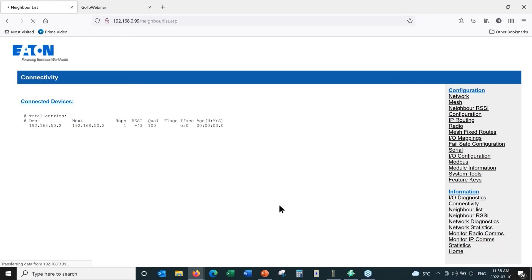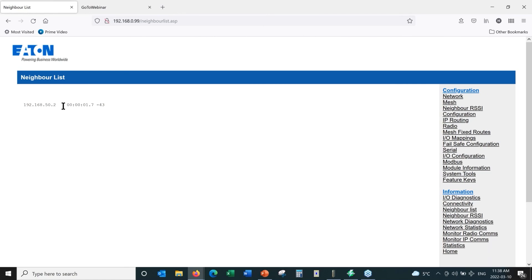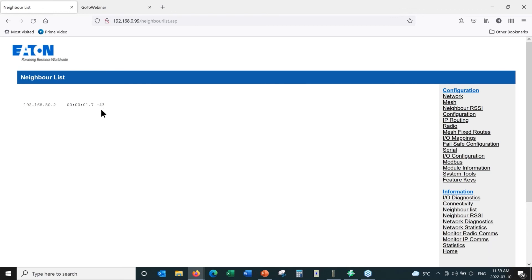The neighbor list shows a single remote radio with a radio IP address of 50.2. It has been online — the last transmission received was 1.7 seconds prior to clicking on this page. This tells you the last time an update was received from that radio. If the update time is set to 10 minutes, you might see values like five or eight minutes, but you should always see a value less than the update time. The RSSI is negative 43. Normally in a larger network, you might see 20 or 30 radios with their radio IPs, last transmission times, and RSSI values.